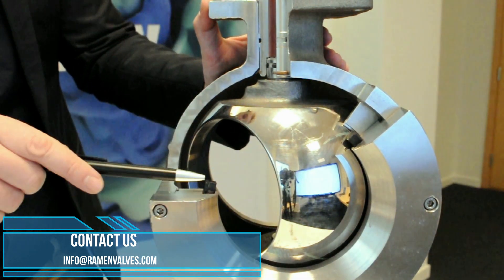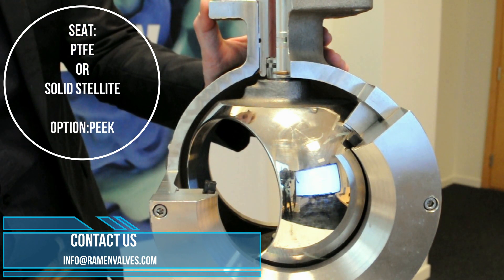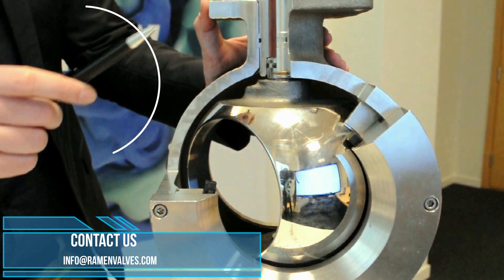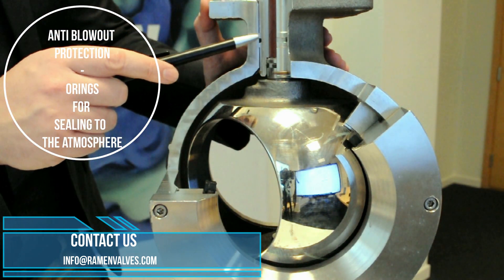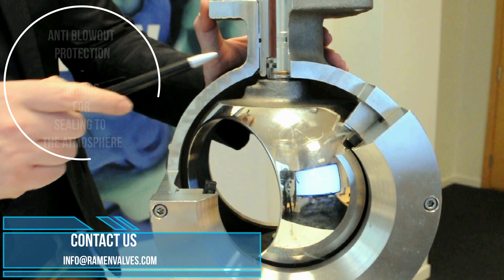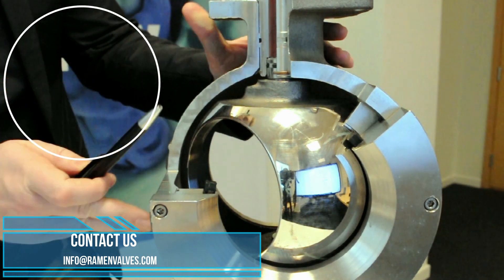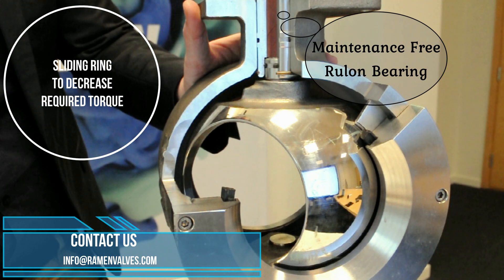Here we have the seat — in this case a PTFE seat — but we can also provide solid Stellite seats depending on the application. We have anti-blowout protection here and two O-rings for sealing to the atmosphere, one here and one here. This is a sliding ring here in white, the purpose of which is to decrease the torque and allow the use of a very small actuator.